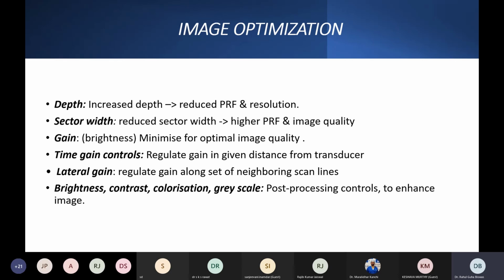Again, the depth is very important. You shouldn't be sending your sound waves to depths which are not required for your interrogation, because the higher depth you select, once again, remember the sound wave will need more time to come back, and that will reduce the image resolution.